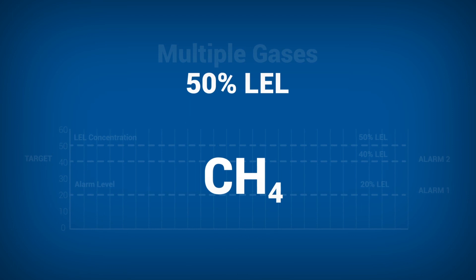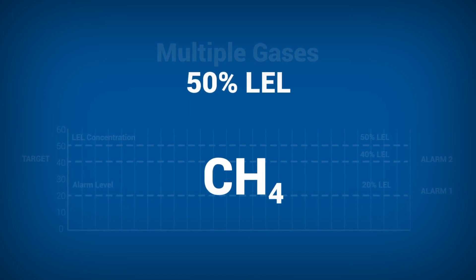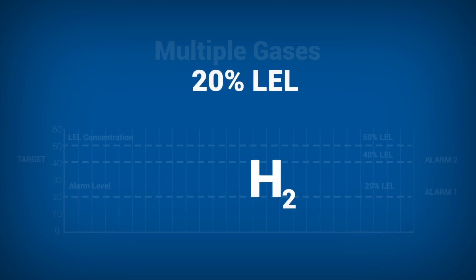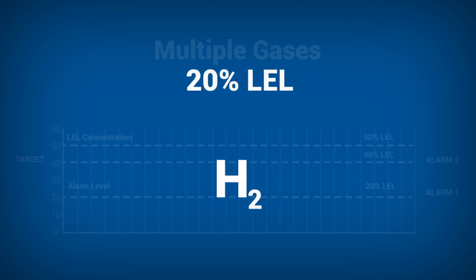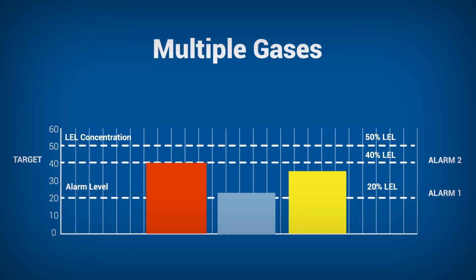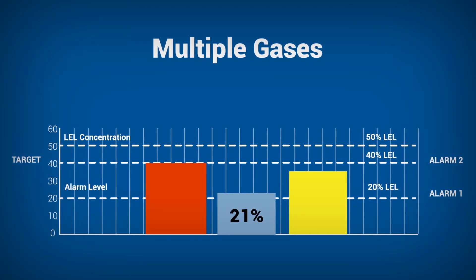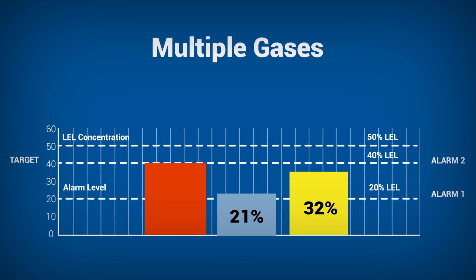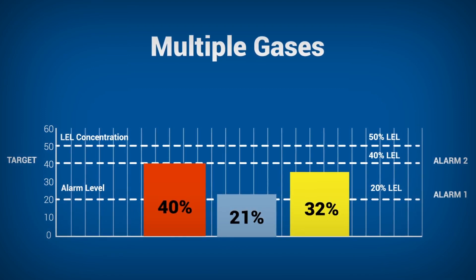For the final test, all sensors were calibrated to 50% LEL methane and exposed to an environment with 10% LEL methane, 10% LEL butane, and 20% LEL hydrogen. All sensors reported some level of gas: 21% by the NDIR, 32% by the pellistor, and 40% by the MPS. Only the MPS reaches the important second alarm level, potentially saving lives.